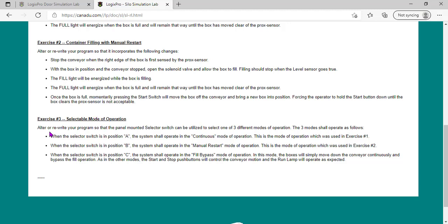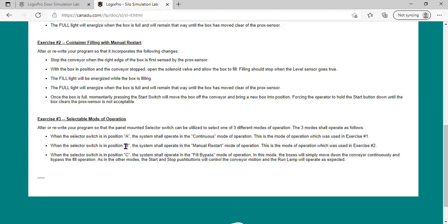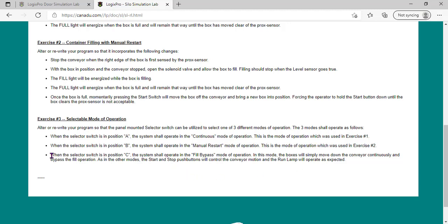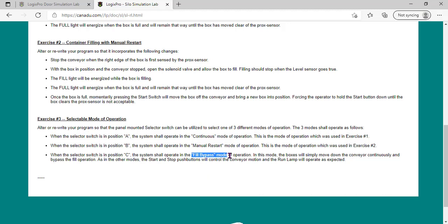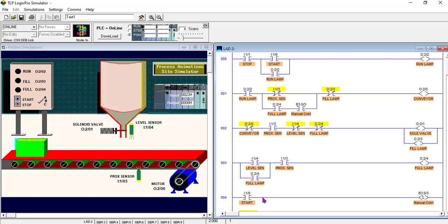The assignment says: select mode of operation. We have to select the mode at which we want to operate. When the selector switch is in position A, the system shall operate in continuous mode - it will be in auto mode, and exercise one will be activated. When the selector switch is in position B, it will manually start and exercise two activates. When you select position C, we bypass the filling - the box will just be traveling across the silo, traveling out, and there will not be any filling. So that will be fill-bypass mode of operation.